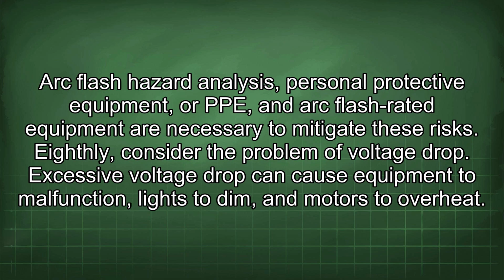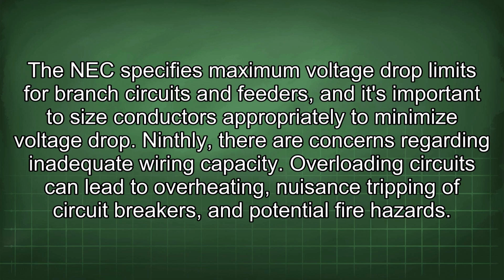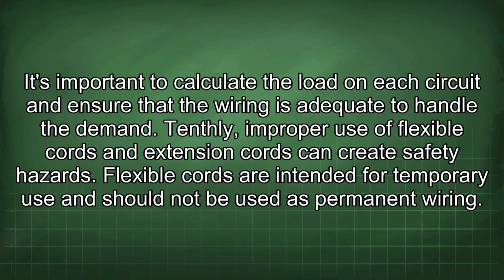Eighthly, consider the problem of voltage drop. Excessive voltage drop can cause equipment to malfunction, lights to dim, and motors to overheat. The NEC specifies maximum voltage drop limits for branch circuits and feeders, and it's important to size conductors appropriately to minimize voltage drop. Ninthly, there are concerns regarding inadequate wiring capacity. Overloading circuits can lead to overheating, nuisance tripping of circuit breakers, and potential fire hazards. It's important to calculate the load on each circuit and ensure that the wiring is adequate to handle the demand.